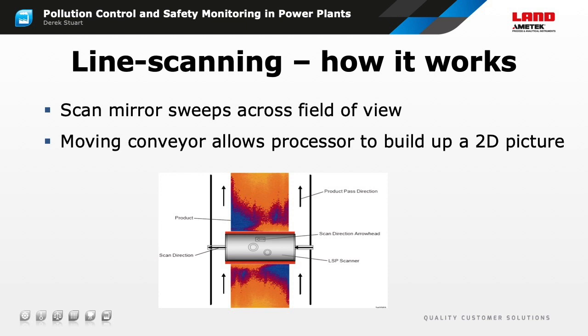A typical instrument can resolve 1,000 points per scan, with as many as 100 scans per second, giving very high spatial and temporal resolution. Line scanning has significant advantages over conventional thermal imaging. It has only a single infrared sensor, so the consistency of temperature measurement is better than an image sensor, which may have over 100,000 separate pixels, each with a slightly different responsivity. It's important to remember that a line scanner, like any other thermal imager, cannot see through the fuel and is limited to measuring surface temperature.